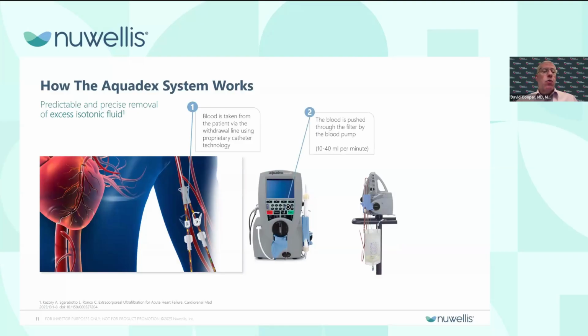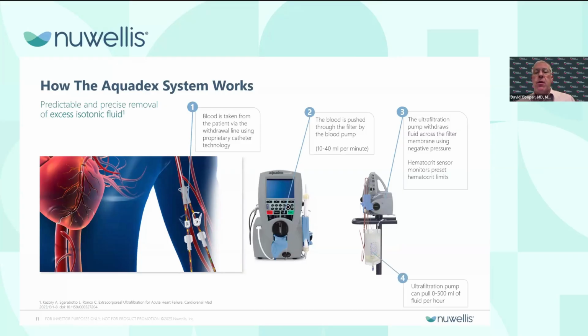So this is how the Aquadex system works. Blood is taken from the patient via the withdrawal line using a catheter. That blood is pushed through the filter by a blood pump at about 10 to 40 mL per minute. The ultrafiltration pump then withdraws the fluid across the filter membrane using negative pressure. And as I said before, there's a hematocrit sensor that monitors the patient's preset hematocrit limits and can help guide therapy. And the ultrafiltration pump can pull exactly 0 to 500 mL of fluid per hour. So very safe, effective, and efficient.